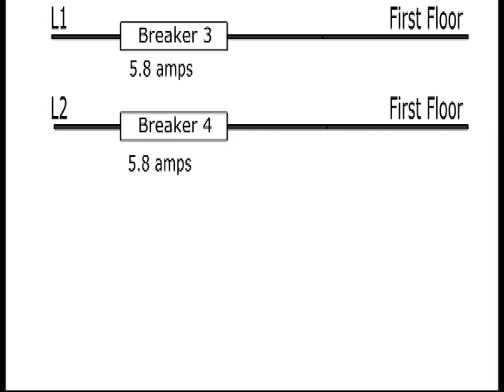If there are three heaters installed, the total current from the breaker will be just 17.4 amps, a little bit over half the capacity of the 32 amp breaker. For practical purposes, we can think that by using 220 volts, the amperage is reduced by one half.